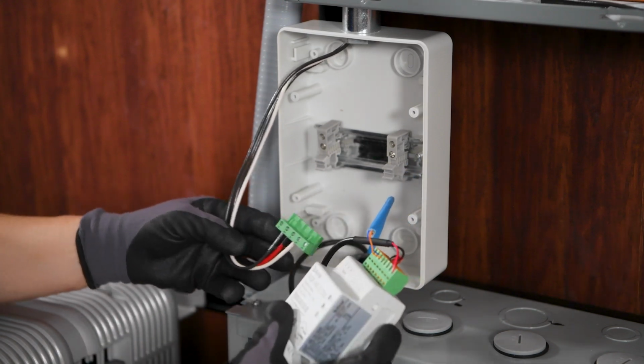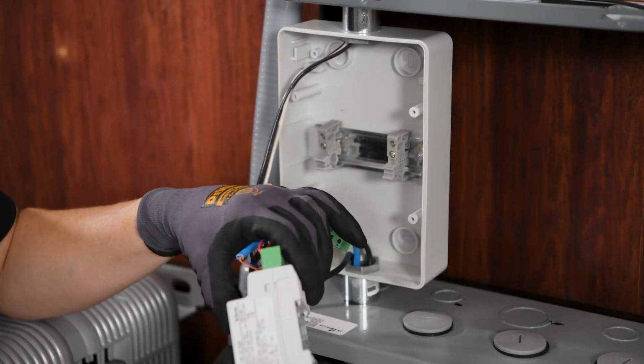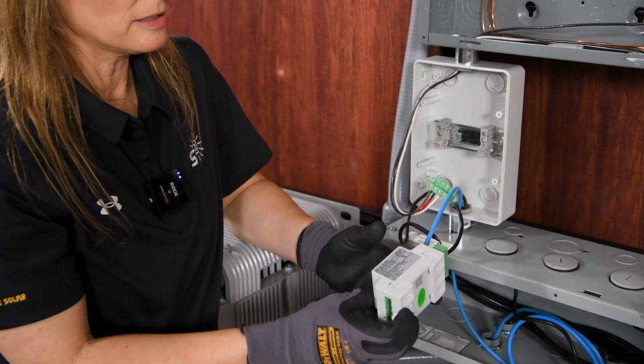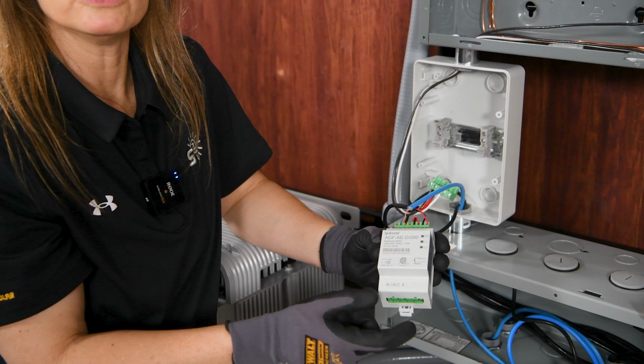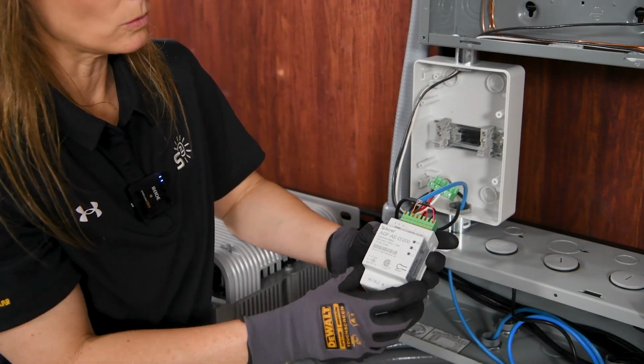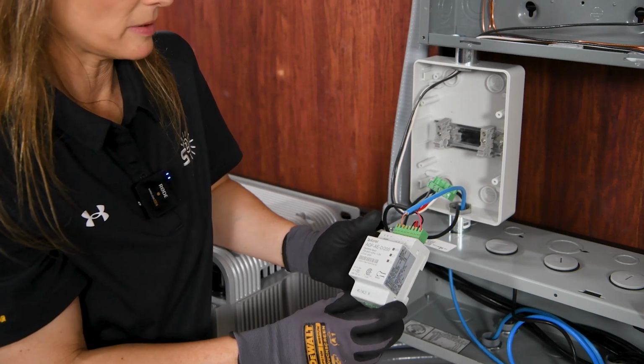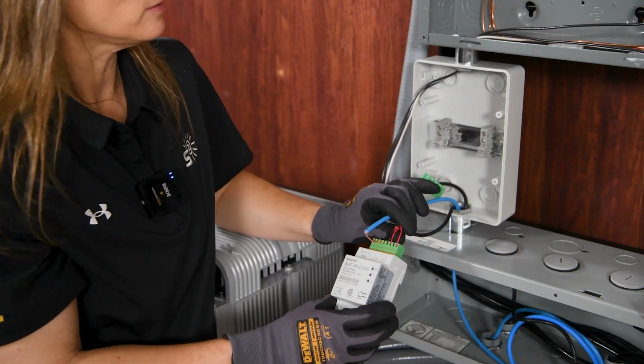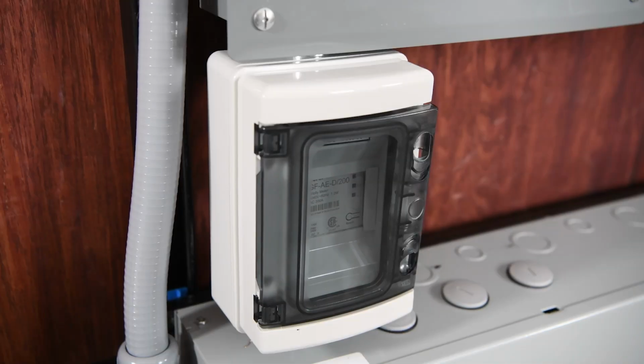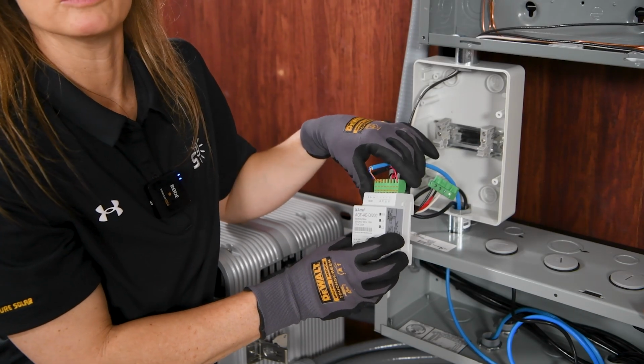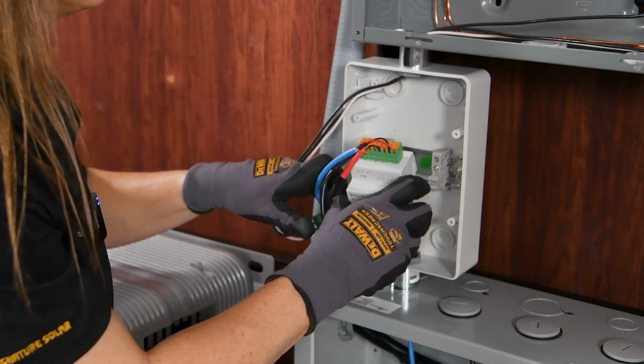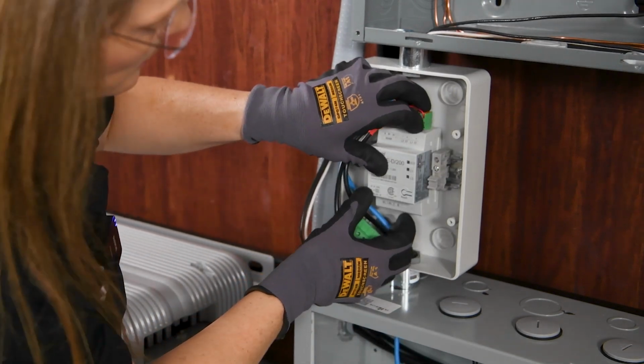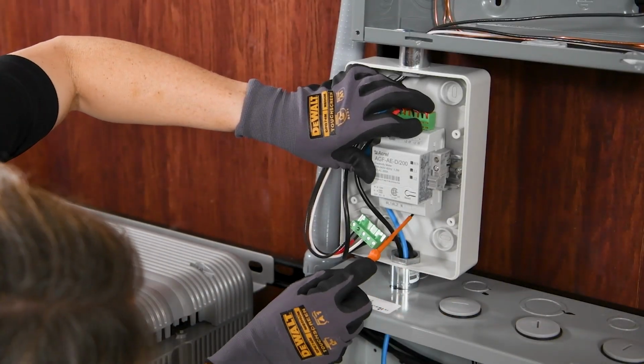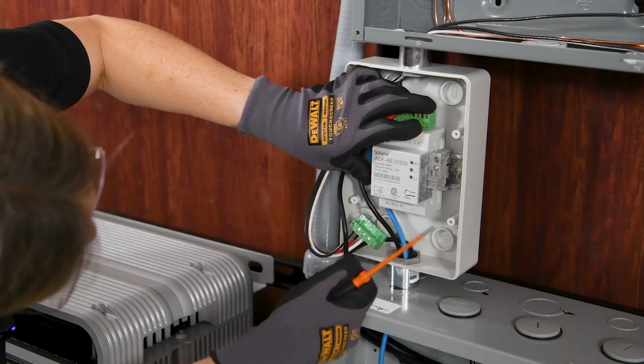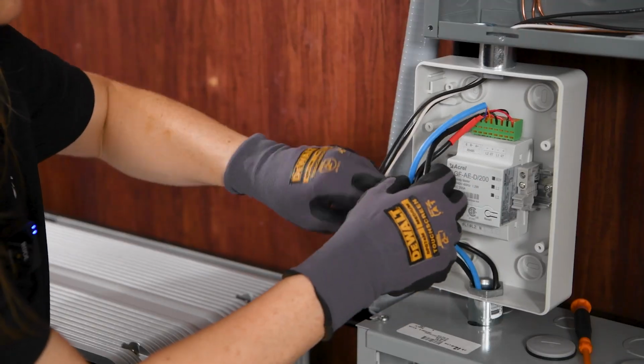Now before we actually connect this, I'm going to show you how to connect the meter to the DIN rail. Your electricity meter is designed to be installed on a DIN rail inside a power distribution panel. Typically, this would be inside your main panel or in an external box outside your main panel. We had trouble finding a DIN rail, so what we did was we found a breaker box that was rated for 600 volts, and we took out the breaker and we installed this electricity meter inside the breaker box. To install this on a DIN rail, snap it over the top, and then it has a clip on the bottom that you just push up to lock it in. We'll do a little bit of wire management here.